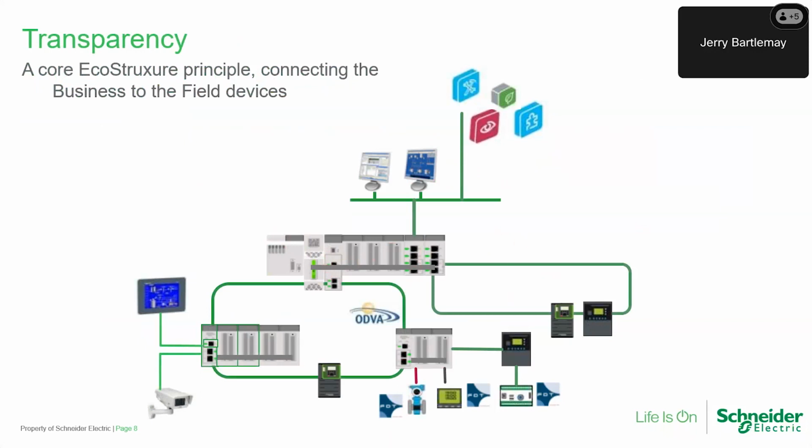But one major innovation in the M580, probably the major innovation, is the addition of an Ethernet backplane. That extends the Ethernet remote I/O system to the backplane of each rack in the system. And that gives us great capabilities. So now that NOC module that we had a couple of slides ago could be connected to that module, connecting the plant network to the Ethernet remote I/O system, and then getting access directly to any of these field devices without the processor's intervention.